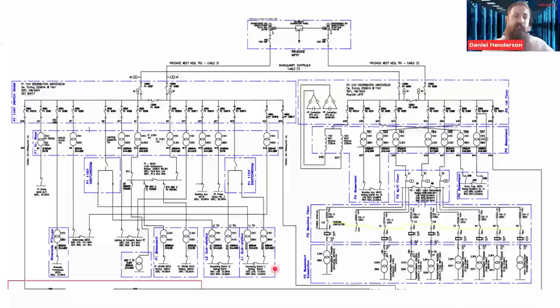So just to give some context on the network, I've got 2 grid connections at 66 kV. These are my assets under my control. These are 66 kV, they are 12 to 24 MVA, and they're capable of managing the whole site load on one of those. So the site's been constructed with N+1 from a reliability perspective. So in the event of a fault or maintenance, I can put all the load onto one transformer and take the other transformer offline to do maintenance or conduct a repair.